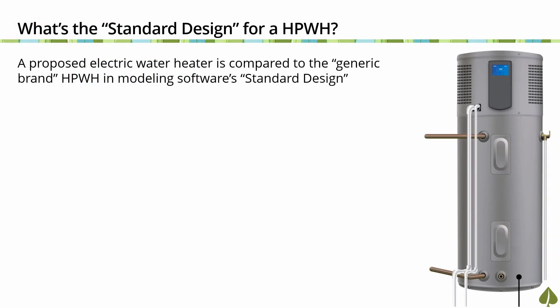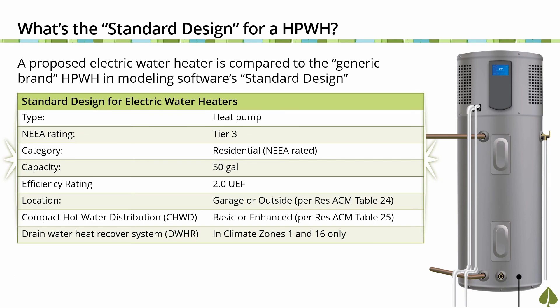When modeling low-rise residential buildings for compliance with the 2019 Energy Code, the standard design for domestic hot water, or DHW, serving individual dwellings is based on the prescriptive requirement found in Section 150.1 C8 and the proposed water heater type being either gas or electric. When the proposed design specifies an electric water heater, the compliance software sets the standard design to a generic brand heat pump water heater with a NEEA Tier 3 rating, a capacity of 50 gallons, and a UEF rating of 2.0. The prescriptive requirement also includes a compact hot water distribution, or CHWD, system using either the basic credit or enhanced credit depending on the climate zone.